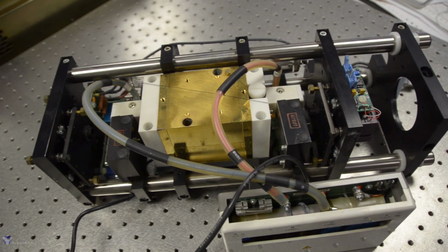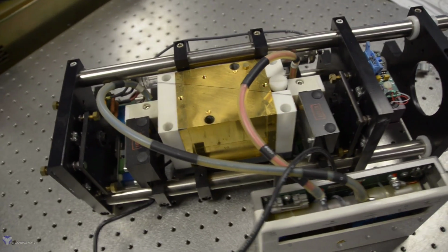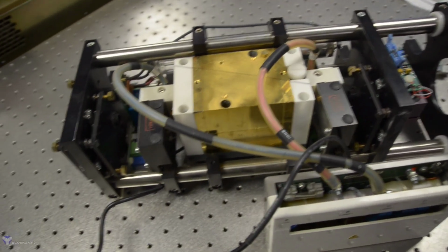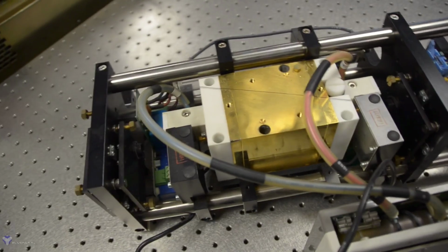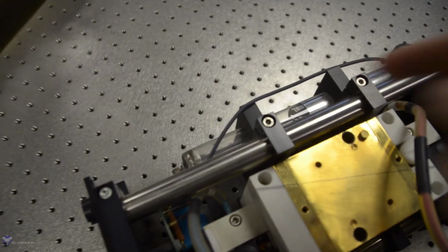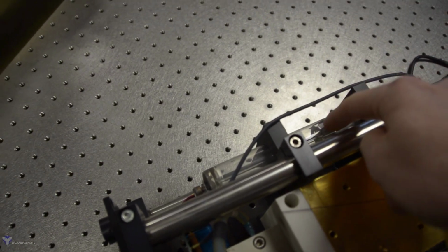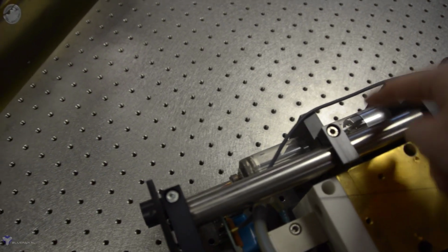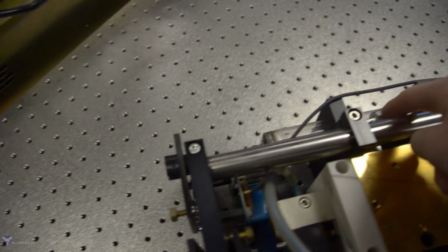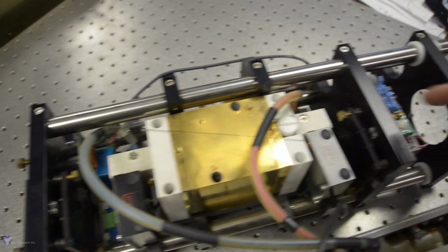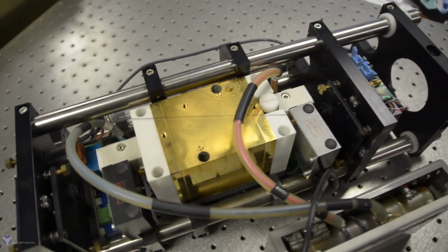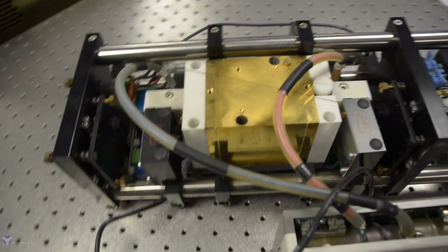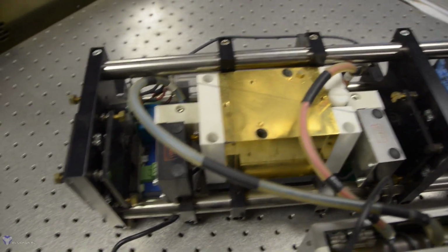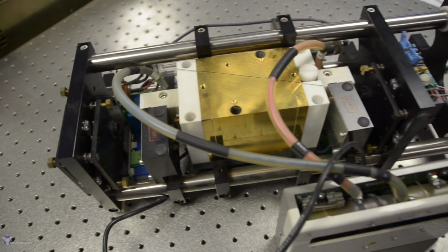So this is the laser head. I already took it out. It looks pretty cool, and let's have a look around and see what we can find. At the back is a helium neon laser, so that's actually an extra laser bolted to the side. And this is a visible laser, 632 nanometers, and that's passed around the back and actually through the whole laser, and that way you don't need to combine the two wavelengths, you just shoot it through the whole laser cavity.